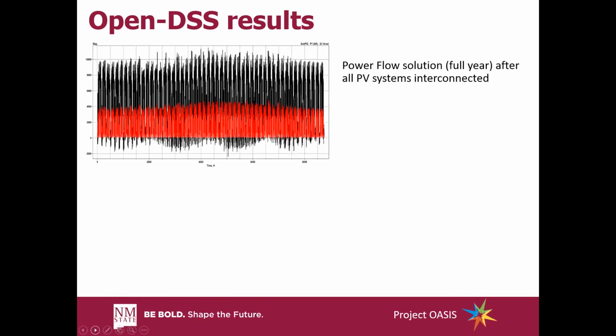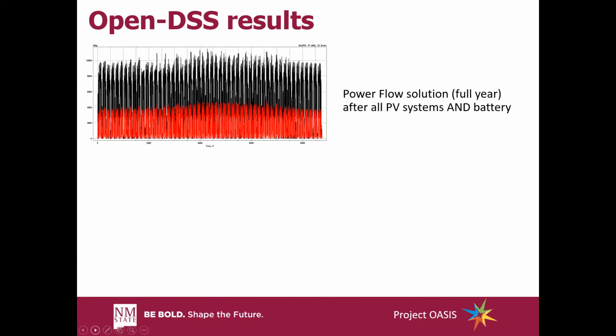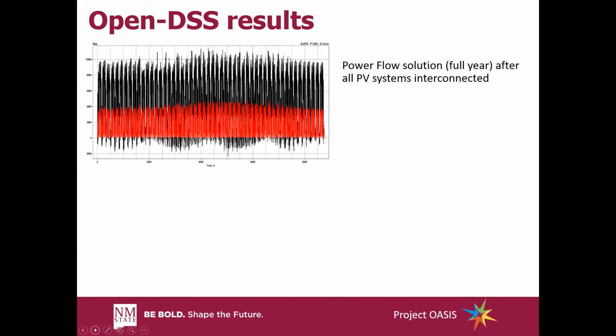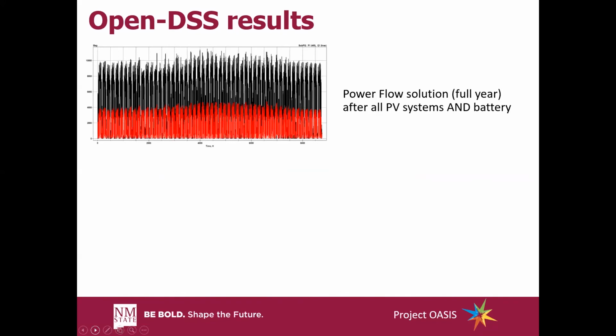This next figure shows a yearly simulation of campus power flow after we have added our PV systems. Negative excursions of real power, shown in black, indicate power which will be exported by the campus distribution system onto the Indiana power system. Since our use case requirement stated that no power export was allowed, we needed to size the battery storage system to absorb all the PV power generated above the campus load on any given day and hour. This next figure shows the yearly power flow solution after we have sized and added the battery PV system.